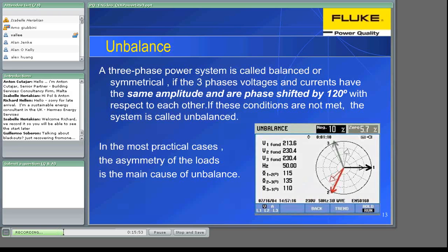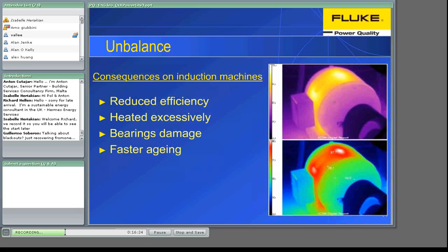Consequences: in a rotating electrical machine, three kinds of problems can be faced owing to the imbalance. First, the torque is limited by the negative sequence, generating a negative braking torque. A mechanical problem: the bearings may suffer mechanical damage, and stator and rotor are heated excessively, which leads to faster aging. In a transformer, the efficiency is affected. This picture shows a thermographic analysis of a motor checking surface temperature. The voltage imbalance can be one of the causes of motor overheating. In this analysis, we have to take care and consider that the internal temperature, the winding temperature, can be about 10 degrees Celsius higher than what is measured on the surface.